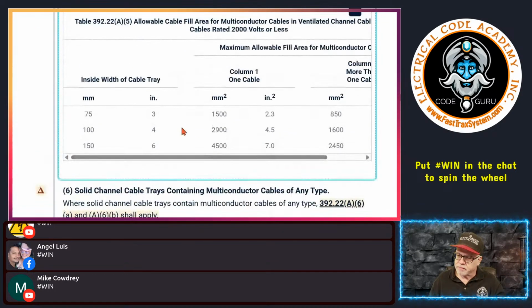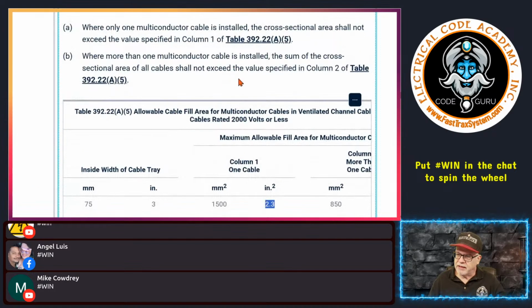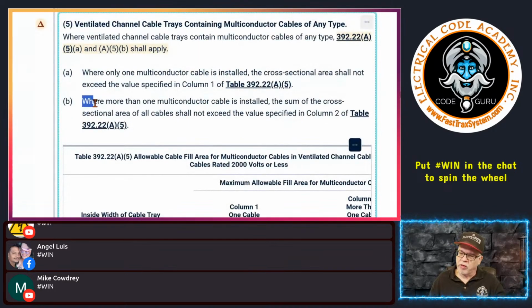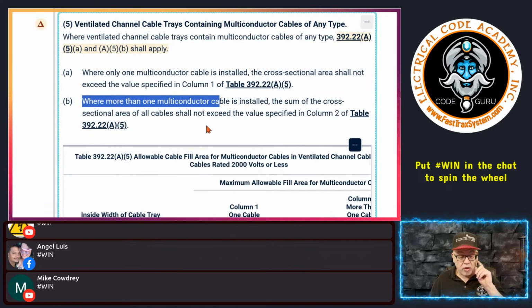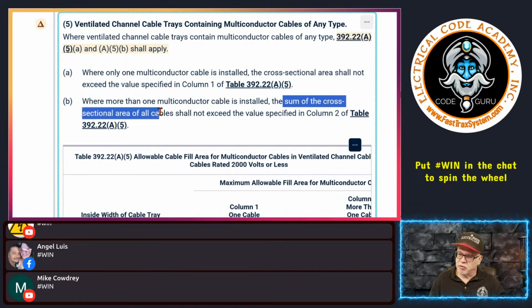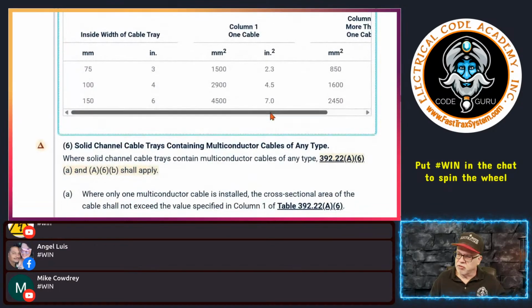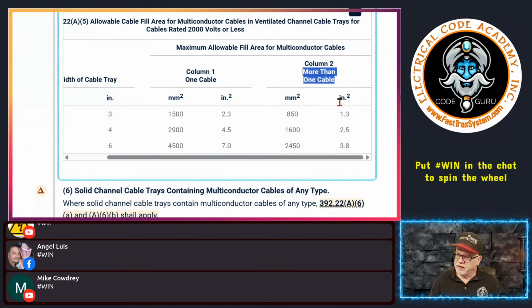And what you will notice is that it only shows a 3-inch, 4-inch, and a 6-inch width type of these channel trays. And it gives you the values in here for fill, okay? That type of scenario, right? So that's the column 1. And then column 2 is saying, when you have more than one multi-conductor cable installed, meaning 2 or more, the sum of the cross-sectional area of all cables shall not exceed the values in column 2. Column 2, as you see here, is more than one. So the 3-inch is 1.3, the fill, and the 4 is 2.5, and the 6 is 3.8. Okay, so that's when you have more than one. So you can't exceed this value.